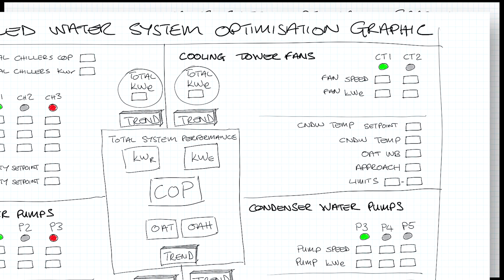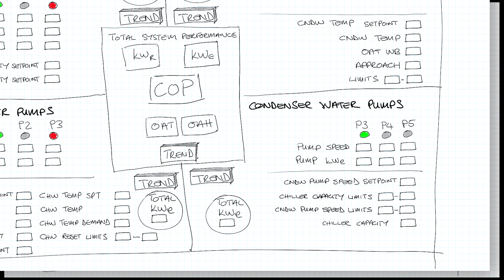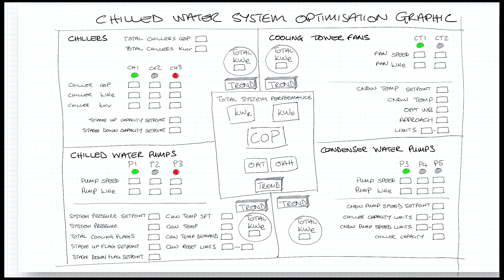On the top right I've got the cooling tower fans - one cooling tower fan running - with all the set points you adjust for optimization of the condenser water temperature. Below that I have the condenser water pumps and the optimization points associated with adjusting their speed. In the middle I've got total system performance: I've added up the kilowatts of electricity for each component - the chillers, the pumps, the fans - and then I have the total kilowatts of cooling. From that I can calculate the COP of the entire chilled water system, plus outside air temperature and humidity, with a trend button.